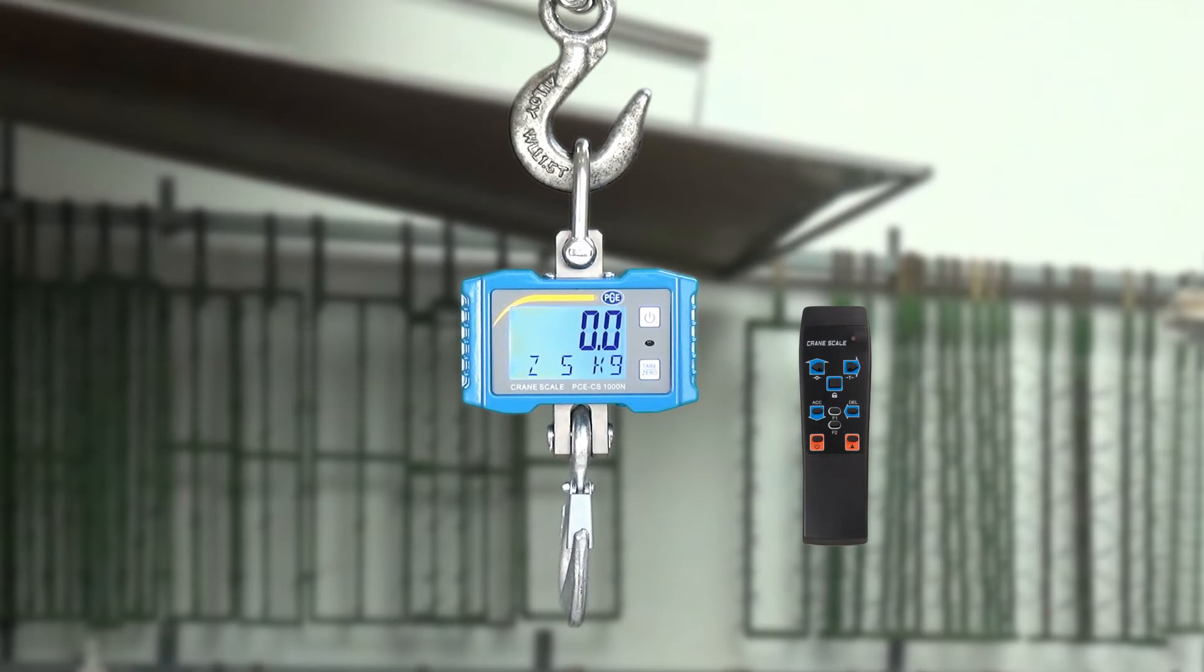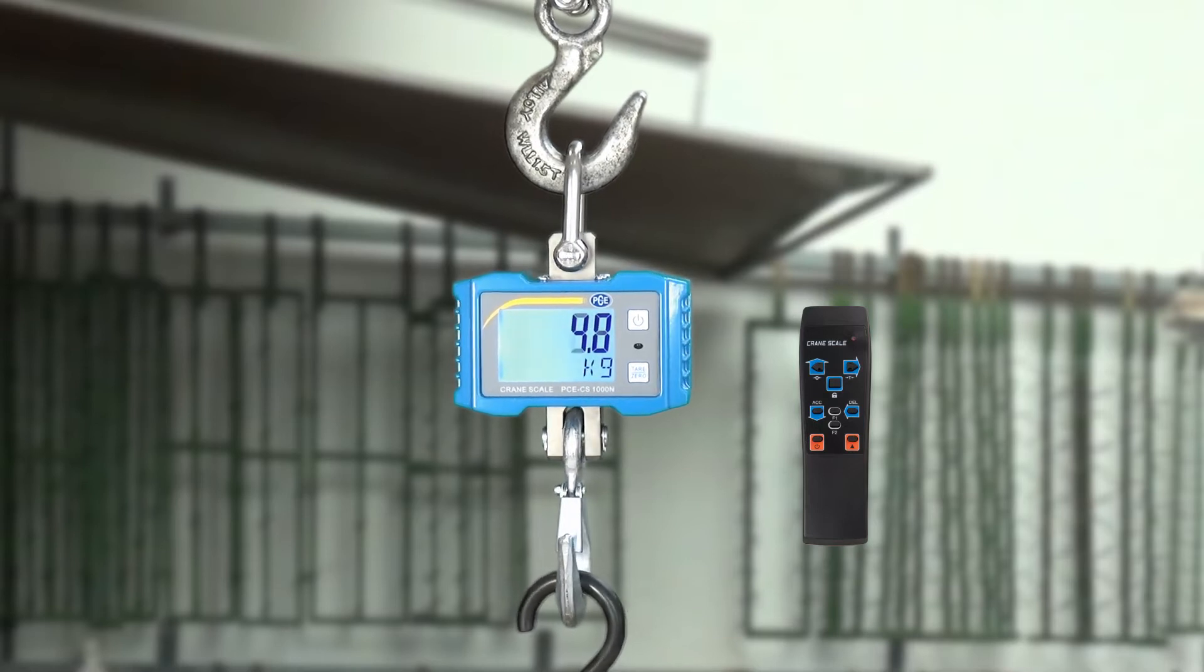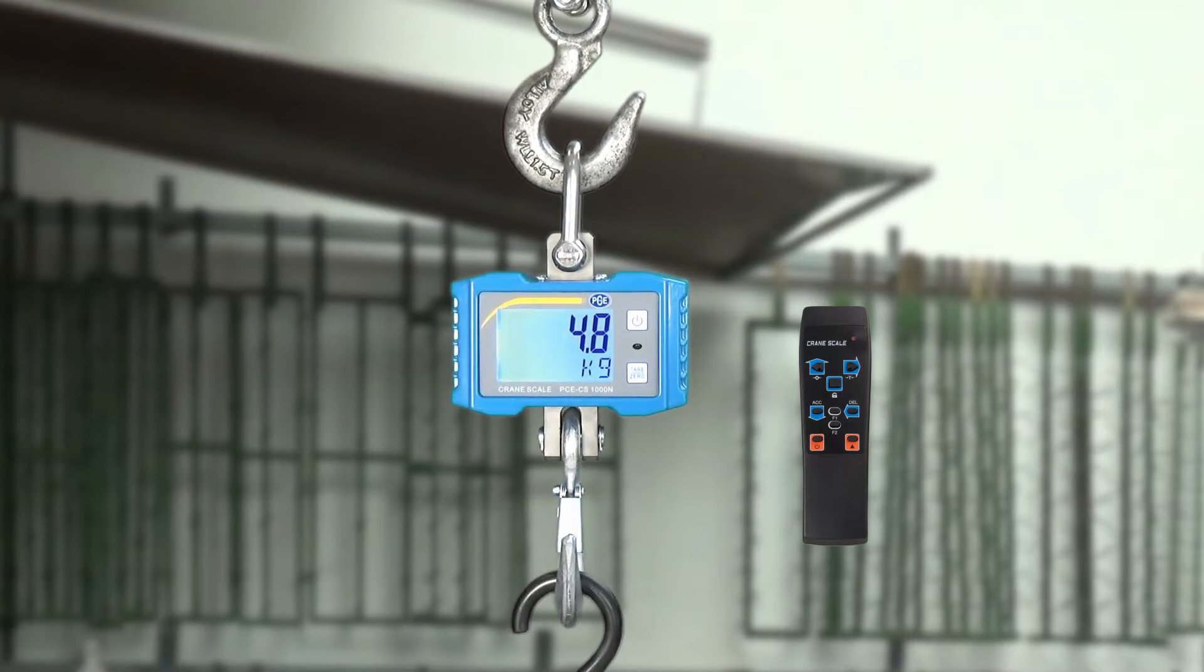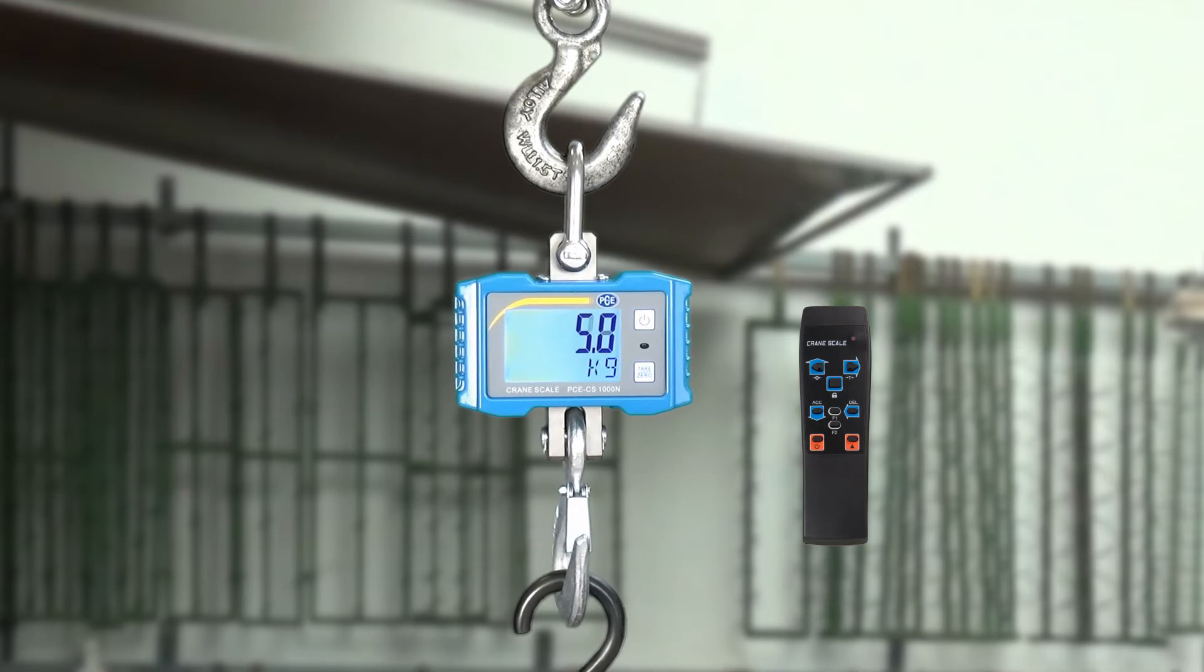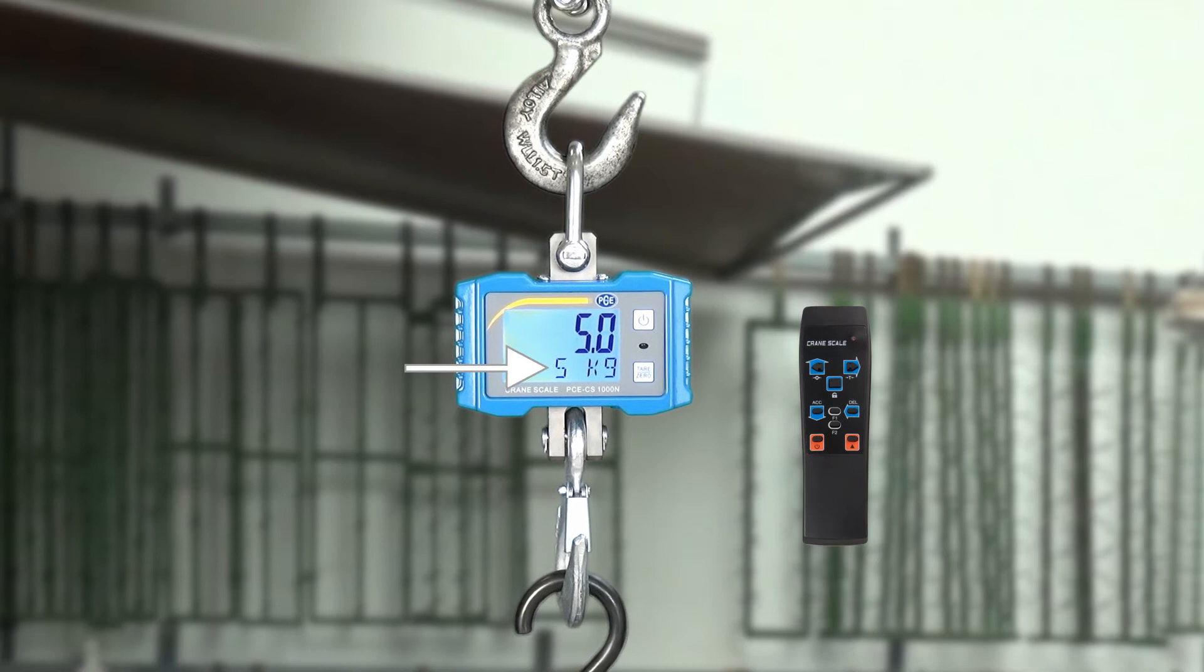First of all I hang a load onto it. As you can see an S appears in the display again. Means that the value is stable. Means that this value is trustworthy and can be used for further measuring.